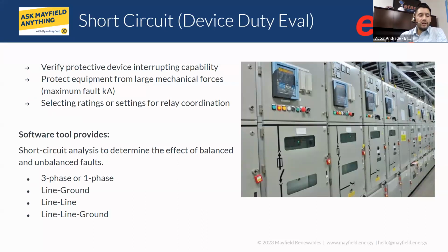Yeah, that's correct. The input information is typically taken from like an AutoCAD file. Okay. So if you have a drawing in AutoCAD, that could be imported into ETAP. And there is definitely additional information that the engineer will have to enter, like the type of protective device, right? Whether it's a low voltage breaker, the manufacturer, the model. Other information that would need to also be collected is cable length, cable size, and very important, sometimes we overlook this, but it's also if we have a tie with the utility, right, what would be the maximum available fault that the utility or the grid that we are connecting to can provide at a given time. So this is collected directly from the utility.